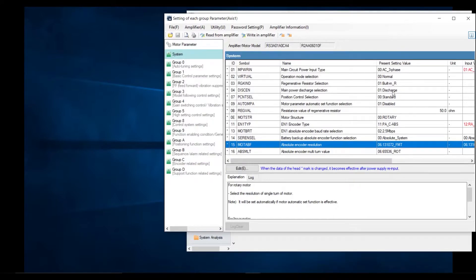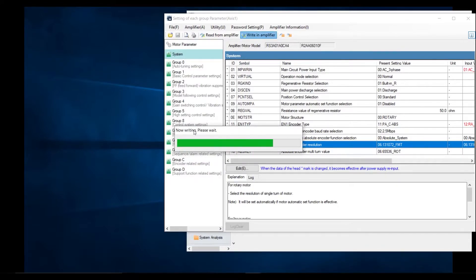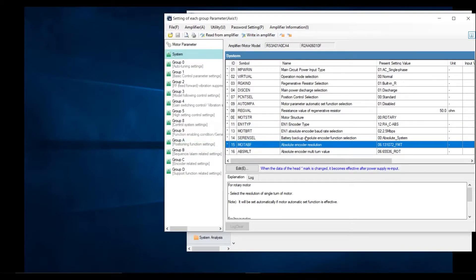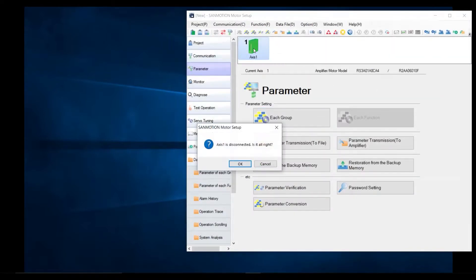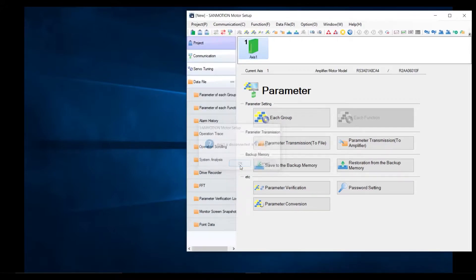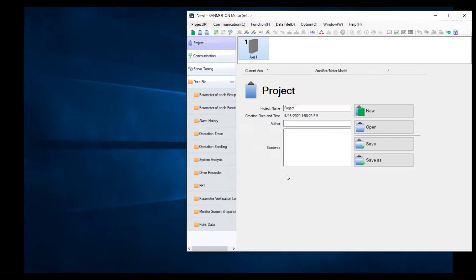Once you have selected all your system parameters that you need to change, you write to the amplifier and once it has loaded, you will need to power cycle your drive. Close this tab, double-click Axis 1, and Axis 1 is disconnected. Click OK. Now you can turn off your drive, connect your motor power connector, and reinitialize your drive, and you should no longer have any alarms on your system.